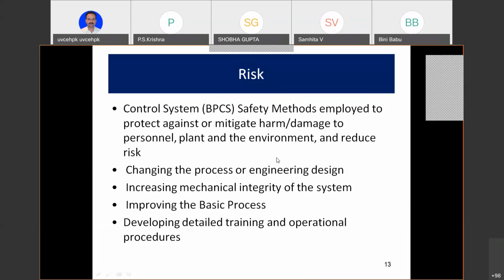Alarm and the pressure will send. Again, that control valve which you saw in that slide, I'm not going back, but you can remember that the controller output went to a control valve. Now in the hazard analysis also, they'll say, if the valve fails because of the air pressure failure, like a power failure, what happens? The valve has to shut or open. We have to configure that. And we'll say, yes, it has to shut. In some cases, where cooling water is involved, cooling a reactor, what happens if the instrument air fails? You'll say the valve must go into open position. So all the configuration is part of the hazard analysis which we do, and the operation included.